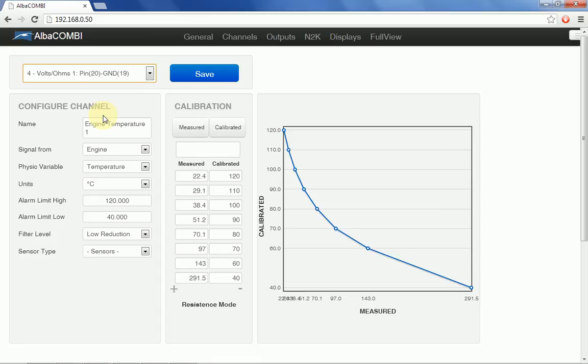Basically, the AlbaCombi is pre-configured to certain calibration parameters, but you can change it to mimic anything. Say that this unit is pre-configured as engine temperature number 1. It says that the signal is coming from an engine. It's measuring temperature in degrees centigrade. It is 120 ohms, 120 degrees high alarm, 40 degrees low alarm, filter level, which is the smoothing of your input, and you can select a type of sensor coming from it. So we can select a 40 to 120 centigrade sensor, or 50 to 150, or we can define our own sensor.